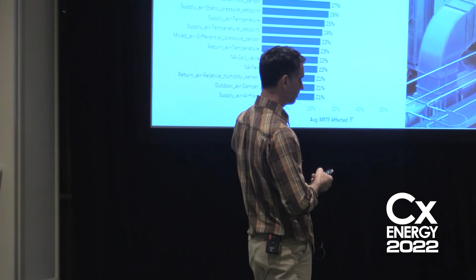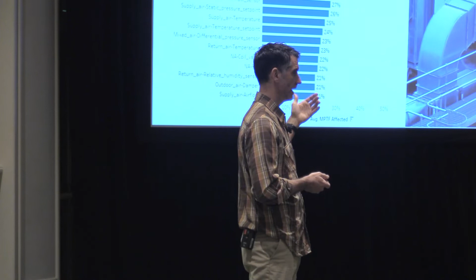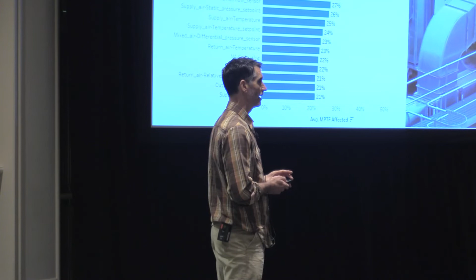One of the things that is kind of interesting when you look at it at this scale is, as I mentioned a couple times now, that with the FDD tools, sometimes they can nail you down to a specific root cause or a specific component that is a root cause, versus more generally saying, hey, a parameter's out of whack, you need to go find out what that root cause is. It tends to be more at the top end, the examples where you don't get that full root cause diagnosis. So, for what you're going to see on these, you can expect the most common faults here to be the ones that are really going to need a bit of extra digging to actually find out what that cause is.